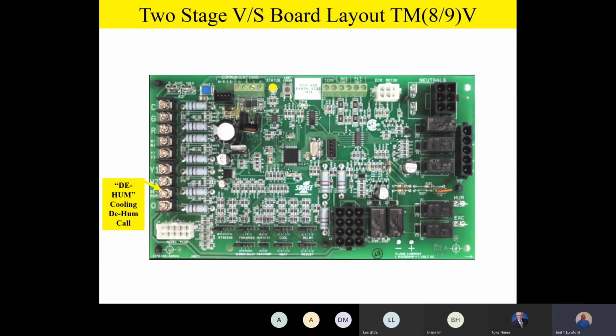It's a dehumidification function. Now watch this. If the humidistat jumper that we're going to talk about in a little bit is in the no position, it ignores that terminal. So if you don't want to use that dehum function with a humidistat hooked up to it in the cooling mode, make sure that humidistat jumper is in the no position. Because if it's in the yes position and you don't have anything hooked up to that terminal, guess what? You'll never get above 85% cooling airflow on a cooling call. Any questions on that?